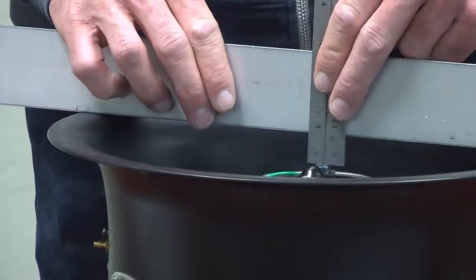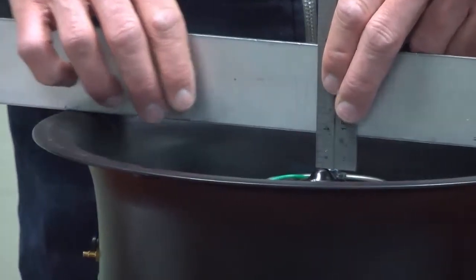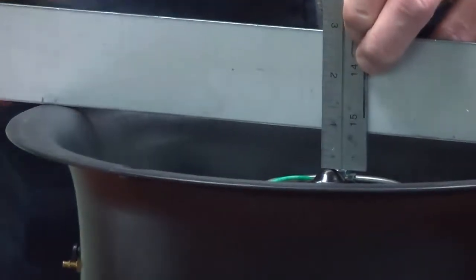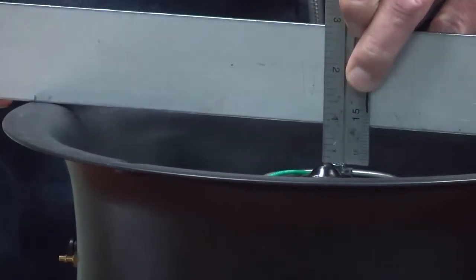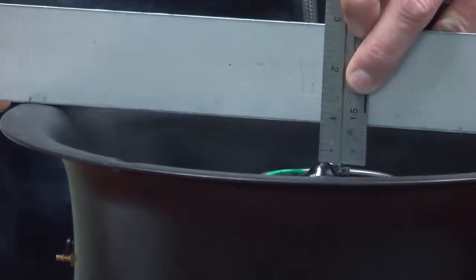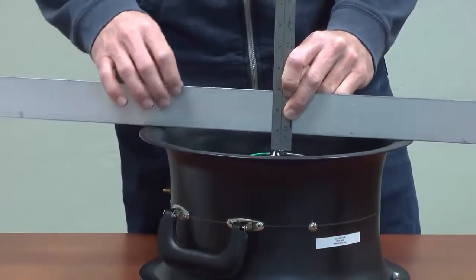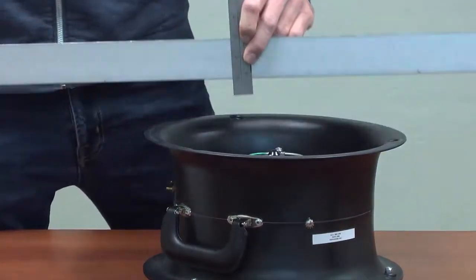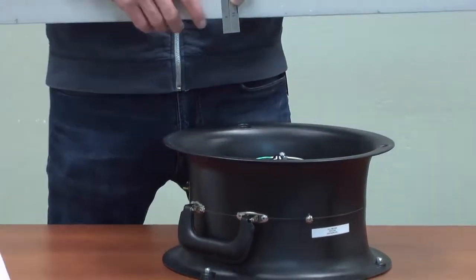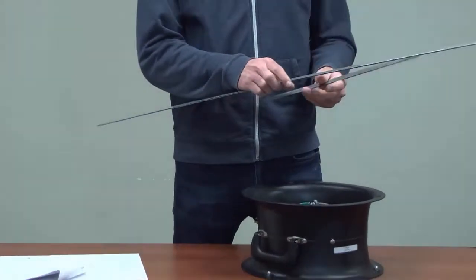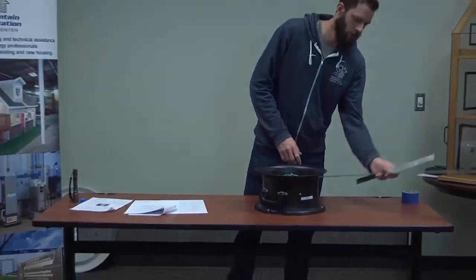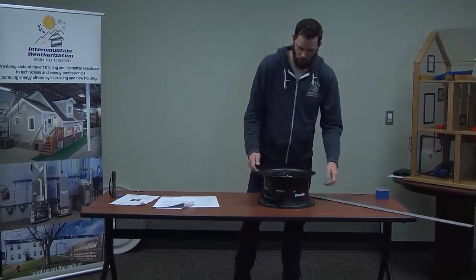So I'll set my ruler across. Take my measurement. And it's about 3/4 of an inch. So in the range on the Duct Blaster, we need to be between 5/8 and 7/8. So we're right in between. So this one passes the flow sensor position test.